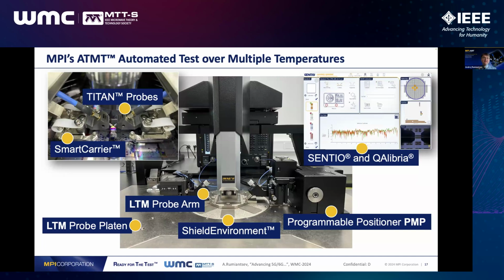So the next slide demonstrates a simple implementation of a two-port measurement system with automated test over multiple temperature solutions. As I mentioned before, it incorporates several hardware and software parts. On the hardware aspect, let me start with RF probes.